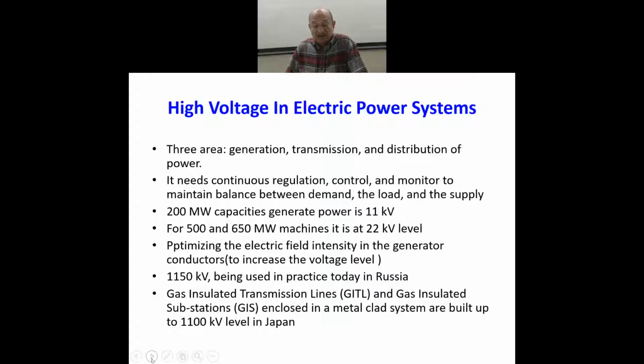the power is the voltage at which it is being generated, that may be 11 kV or 22 kV, is enhanced. It is stepped up for transmission purpose, because for transmission at 22 kV, it is not advisable. We'll see how it is. It may have a lot of losses because the current will be high, etc. So for transmission, we need higher voltages. And for transmission, as I mentioned, we have in the world gone to 1150 kV.